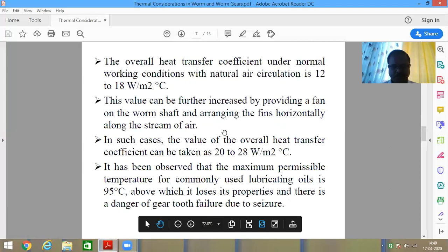It is given that a worm gearbox with an effective surface area of 1.5 meters square, capital A, is operating in still air with a heat transfer coefficient of 15 watt per meter square degree Celsius, K is given. The temperature rise of the lubricating oil above the atmospheric temperature is limited to 50 degrees Celsius. That means it is T minus T0, the difference between the temperature of lubricating oil and the temperature of surrounding air, given as 50 degrees Celsius.